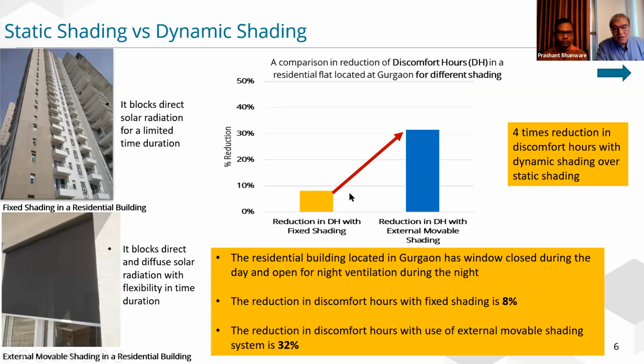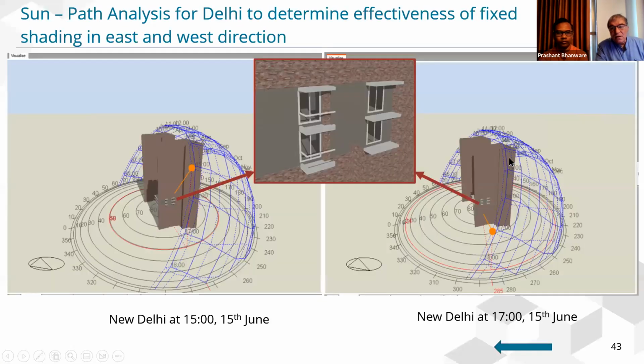So here you see, for instance, at 3 o'clock or 5 o'clock in the afternoon, that if you don't have a protection, if you look at the front part, you can see that the windows are not covered at all, even if you have a balcony. So especially at 3 o'clock, the sun is lowering a little bit and is directly heating the windows, and there you reach sometimes something like maybe 700 watt per square meter. If you have a single glass, it will give you almost 600. So you suddenly get, for a window like this, which may have approximately 2 square meters, something like 1200 to 1500 watt, like if you had an electric heater of the same power inside.